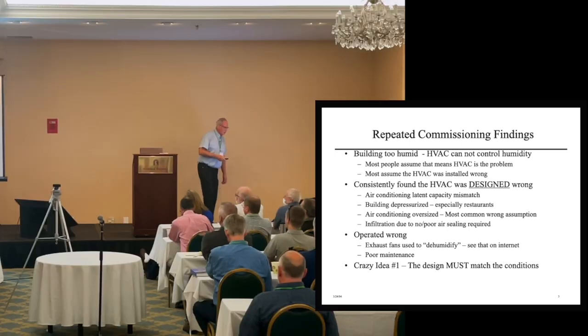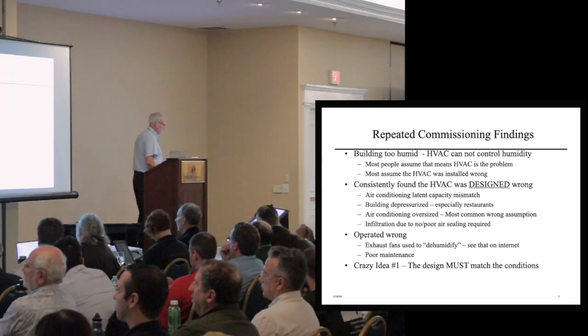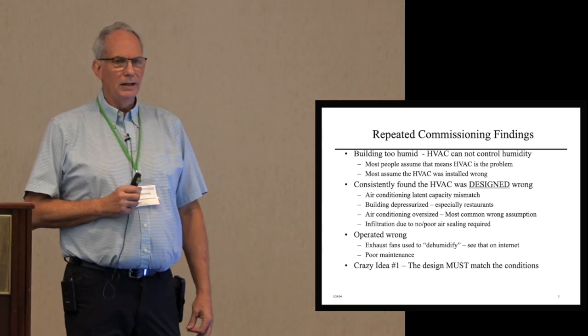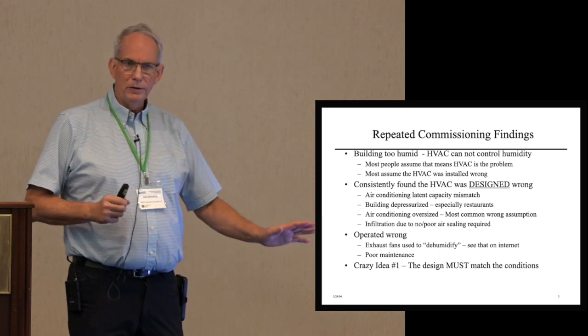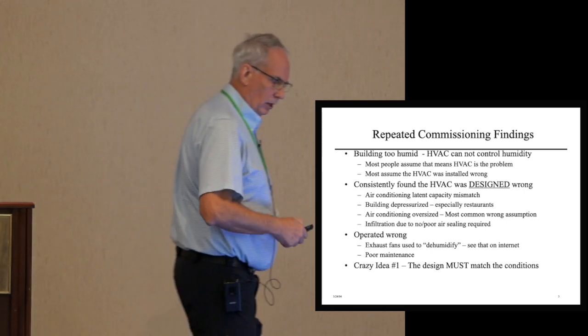Okay? So typically, most people assume that the air conditioning is the problem. After all, the air conditioner is supposed to control the temperature and humidity, right? It's a logical conclusion. And the typical assumption is that the air conditioning was installed wrong. Well, as we started testing, what we consistently found was the air conditioning install was really good in most cases. Occasionally you'd find trouble, usually easily fixed, but the design was wrong. The design could not ever work. And that's what most of this talk is going to be about.